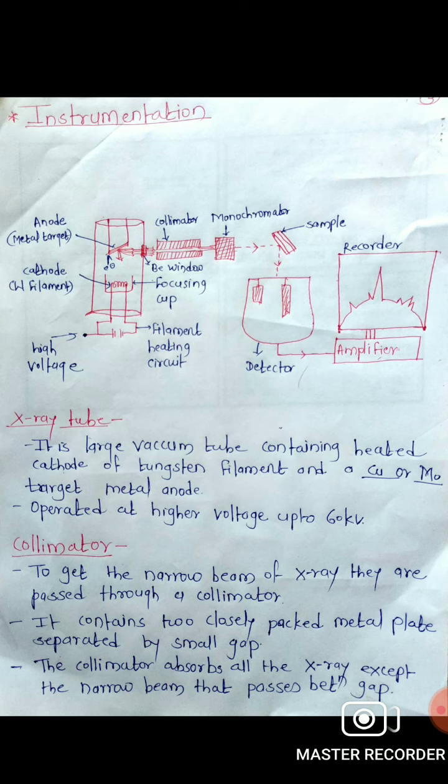This beam of electrons constitutes the cathode stream. The positive voltage in the form of an anode having a target metal is kept near these electrons. When the tungsten filament supplies electrons towards this anode, the electrons hit the anode and it generates the X-ray radiation. After heating it produces the X-ray radiation.